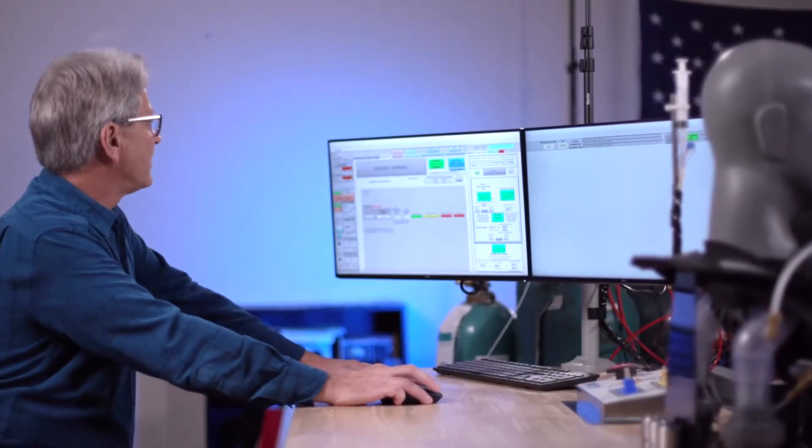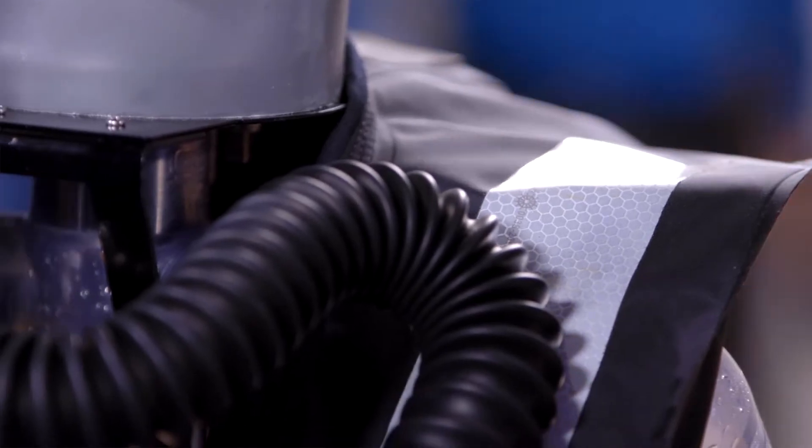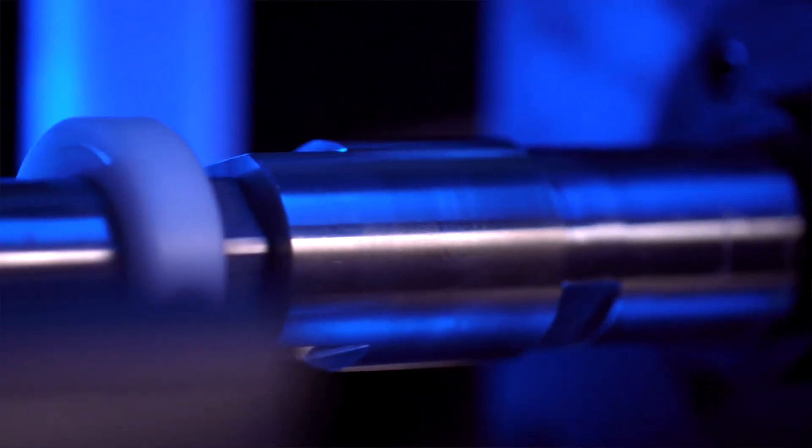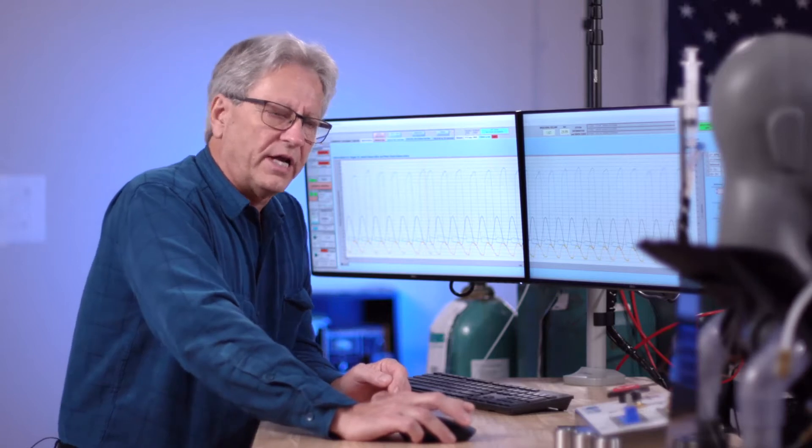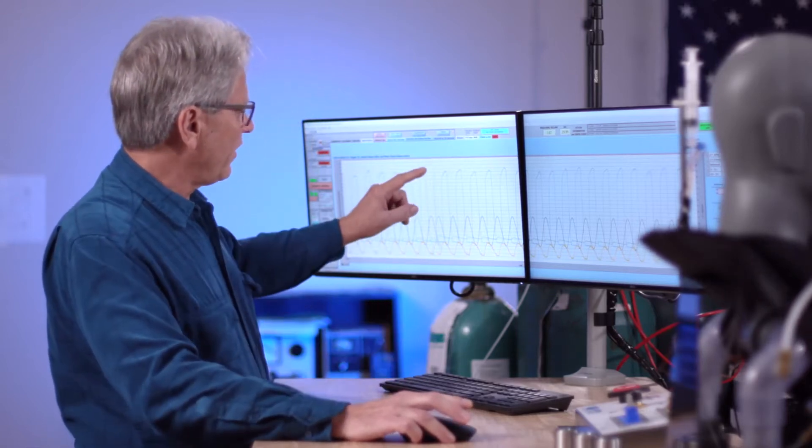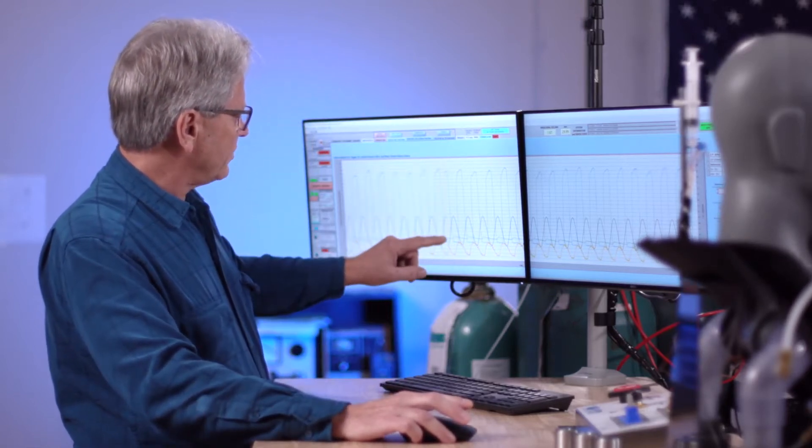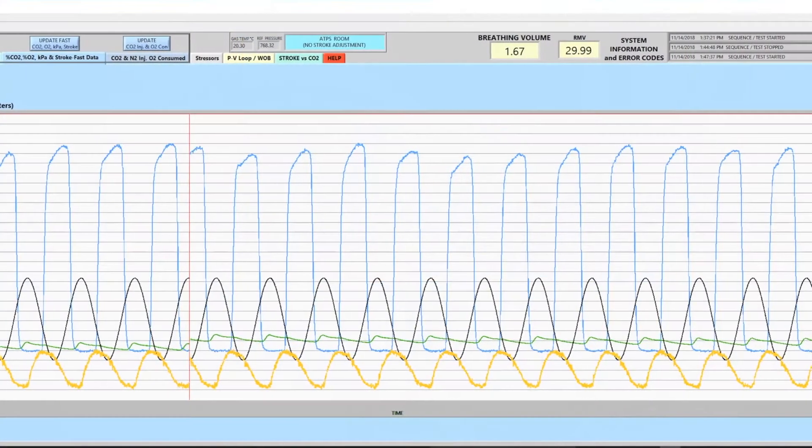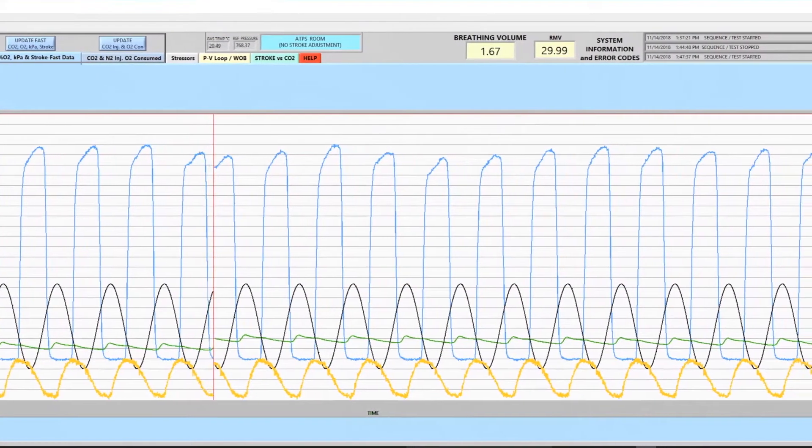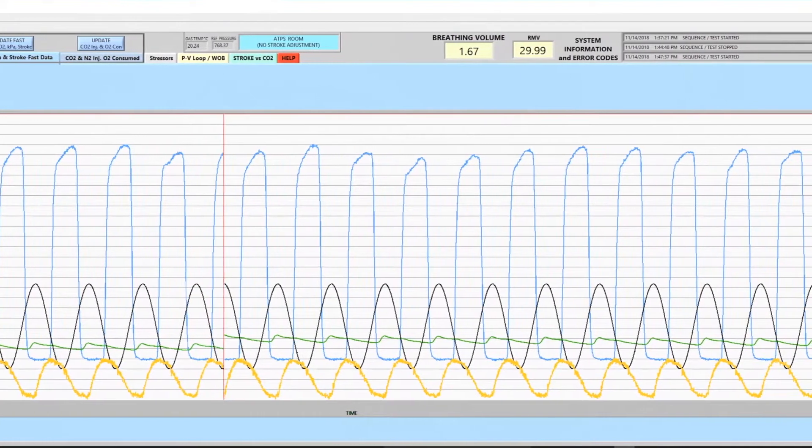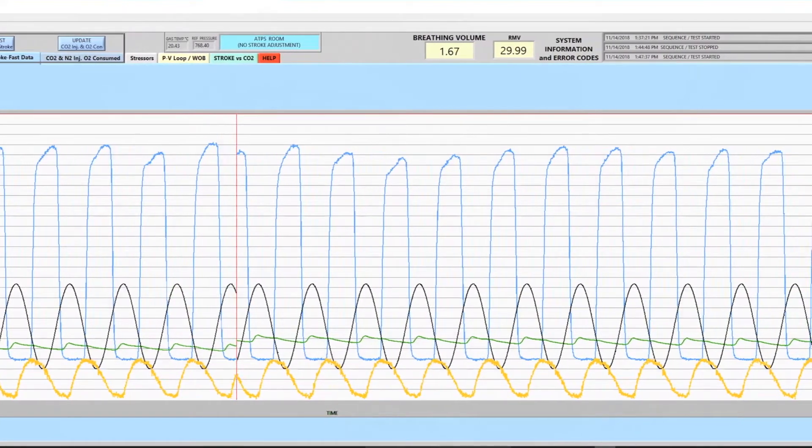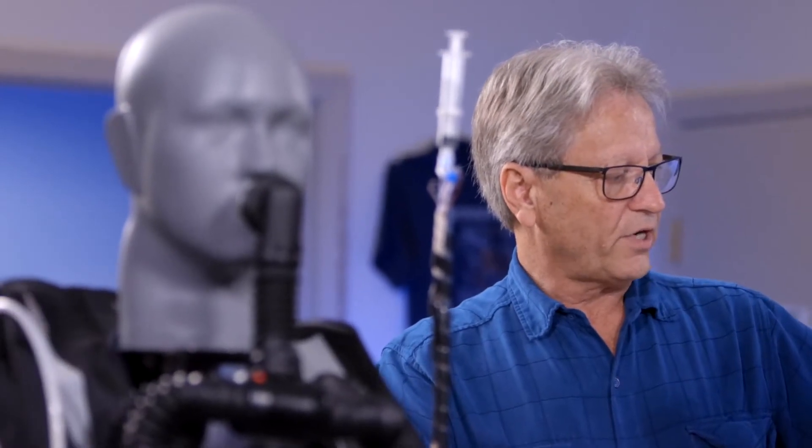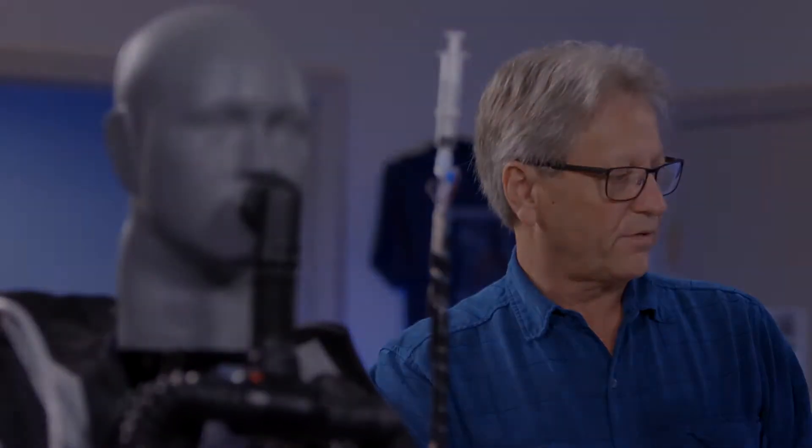As the gas begins to flow into the apparatus and the breathing machine begins to cycle, we have 500 hertz data coming from the carbon dioxide and oxygen analyzers, tracing on the screen in blue for carbon dioxide and green for oxygen. The black tracing is the piston sinusoidal movement and the gold is the pressure differential at the mouth.